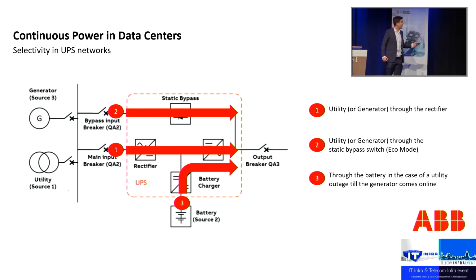Before jumping there, I just want to share with you the operation modes of the UPS. So typically a UPS has 3 operation modes. One is the normal operating condition, when I have the generator or utility available, so I'm operating on the rectifier and inverter, right? So this is the normal operating condition. Now, in case I do not have the generator and utility, I'm going to switch to the batteries. And I'm going to supply the critical loads from the batteries through the inverter.